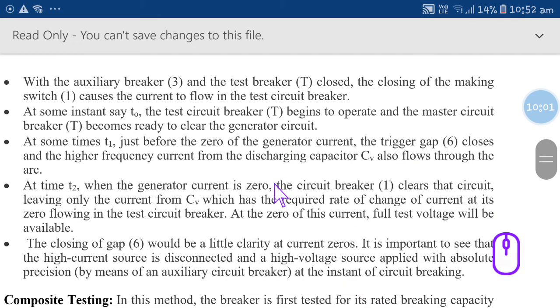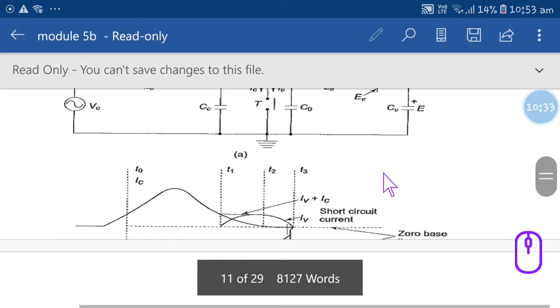And once the auxiliary circuit breaker 3 and the test circuit breaker are closed, what happens? The switch 1 causes the current to flow. Actually it starts from T0, goes to T1, and next will be T2. At T0 the circuit breaker operates, at T1, so what happens here? Here the main current will flow at higher frequency, and at T2 the generator current will be 0. Circuit breaker 1 will clear that circuit. So directly they have specified it here. You can see this also.